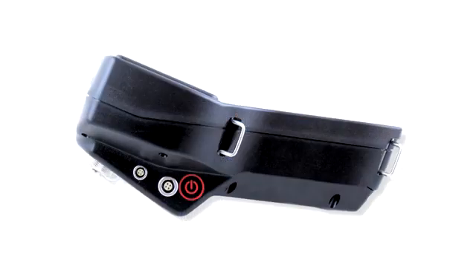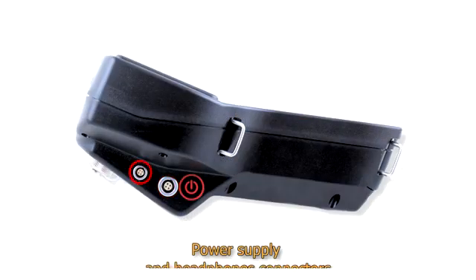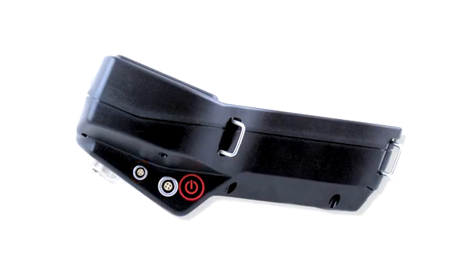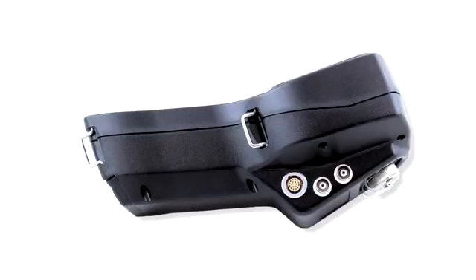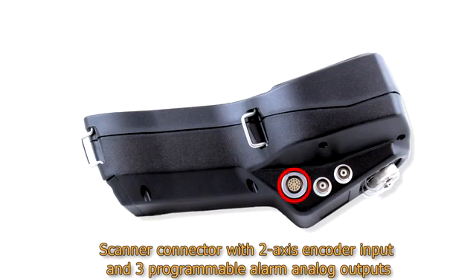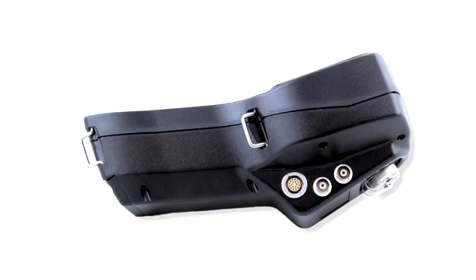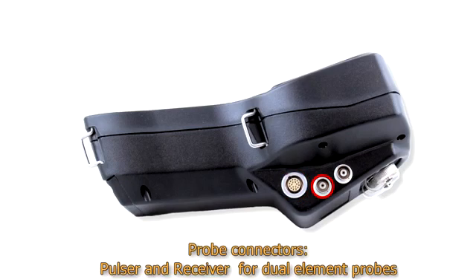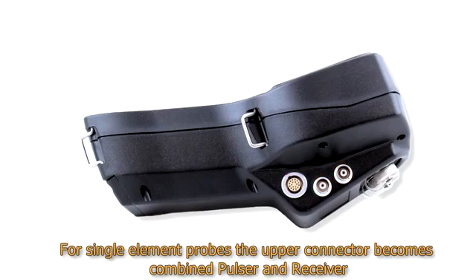On the left panel, the raw power supply and headphones connectors, and the power on-off button. On the right panel, we can find the scanner connector with 2-axis encoder input and 3 programmable alarm analog outputs, and probe connectors, pulser and receiver for dual element probes. For single element probes, the upper connector becomes combined pulser and receiver.